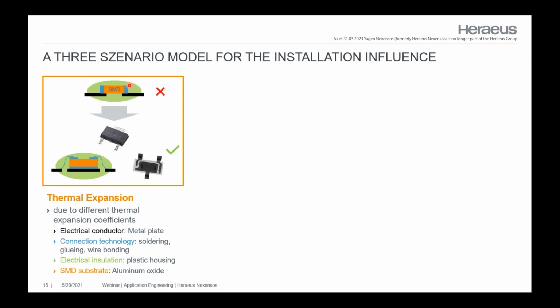If you apply heat to that system, which is typical for a temperature sensor, you get different thermal expansions of the metal parts, and the potting material has a different heat expansion, and the sensor itself has its own specific heat expansion. If you combine epoxies which are quite different compared to metal and ceramic, you can kill your complete system.